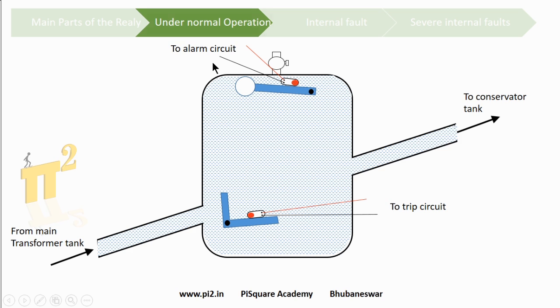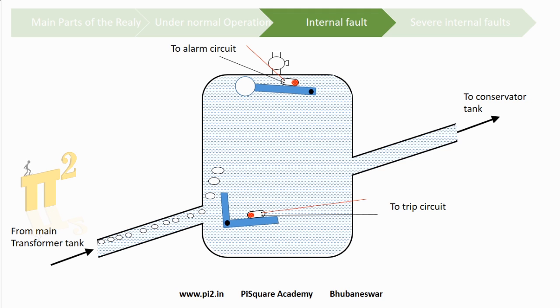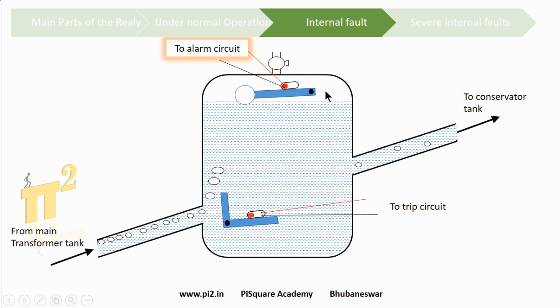Now, if there is a fault, gases are generated in the transformer. As we know, gases are less dense compared to oil, so they try to escape. During this process, some gases get trapped here, which tilts the float down. Hence, the mercury switch is now activated and triggers the alarm circuit.